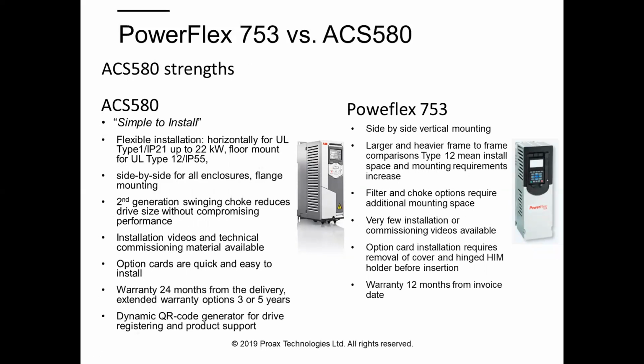This slide is about how simple it is to install this drive compared to PowerFlex. A lot of installation videos and technical commissioning material is available for 580, but compared to Allen Bradley, there are just a few installation videos. 580 is very flexible for installation, horizontally and vertically. For PowerFlex, I see side-by-side vertical mounting, really compact, but compared to 580, especially in type 12, PowerFlex type 12 is large, really large and heavy, because the choke and filter, which are sometimes optional for PowerFlex, need more space. With 580, you don't have to deal with that.